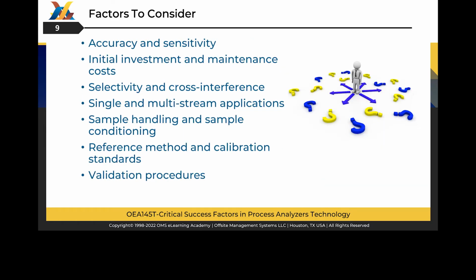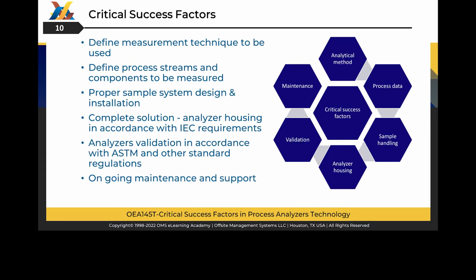The following critical factors shall be considered for analytical method selection and system design: accuracy and sensitivity, initial investment and maintenance costs, selectivity and cross-interference, single and multi-stream applications, sample handling and sample conditioning, reference method and calibration standards, and validation procedures. At the earliest system design stage, the process stream must be appropriately defined in operating conditions and complete sample composition.